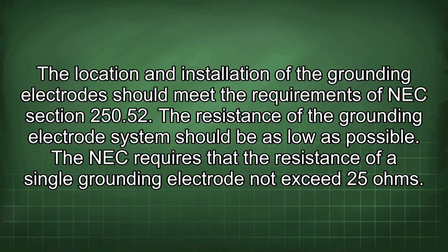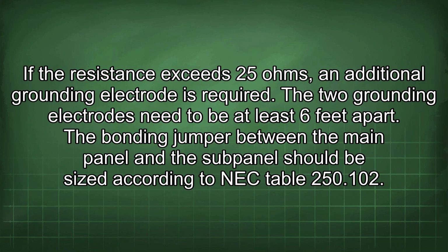The resistance of the grounding electrode system should be as low as possible. The NEC requires that the resistance of a single grounding electrode not exceed 25 ohms. If the resistance exceeds 25 ohms, an additional grounding electrode is required. The two grounding electrodes need to be at least 6 feet apart.